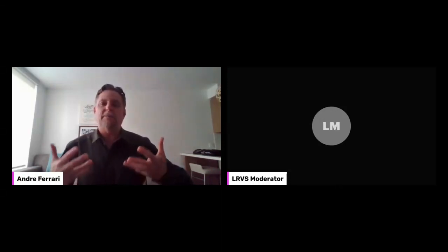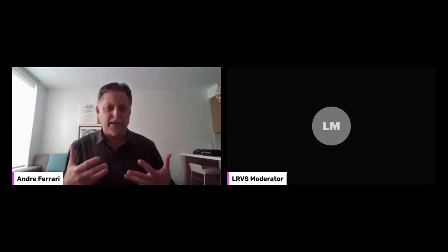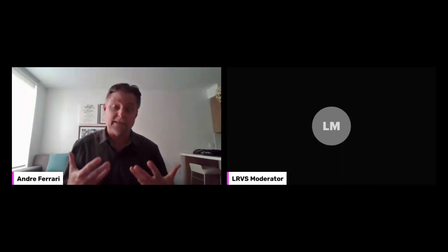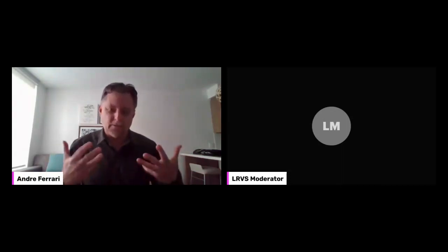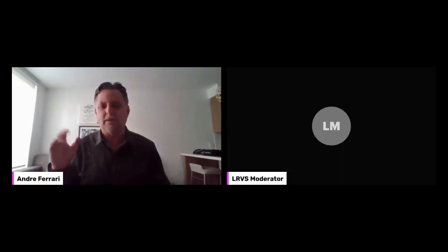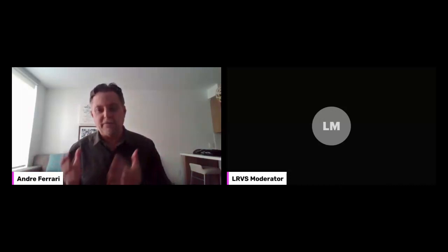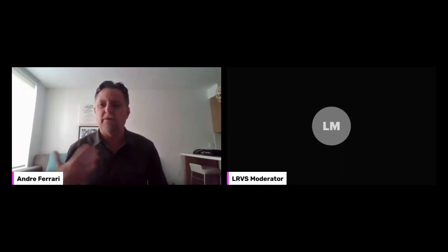But as I mentioned earlier, condition points are points where the transformer has degraded, but it's still functional. It's still working. It's just giving you a little flag there, like I've got a fever. So end of life is specifically a failure. It's just broken down.